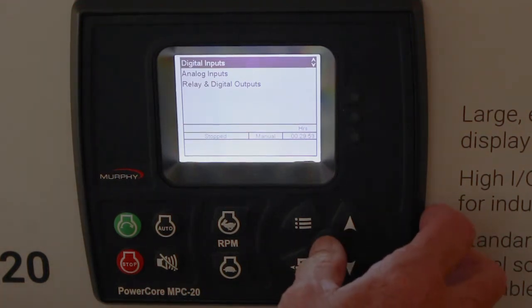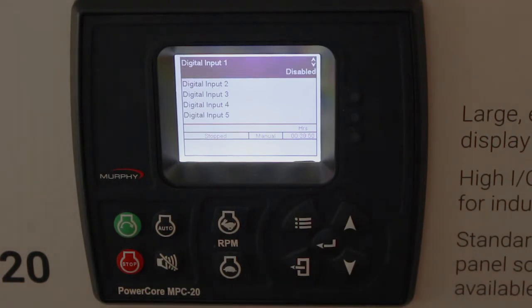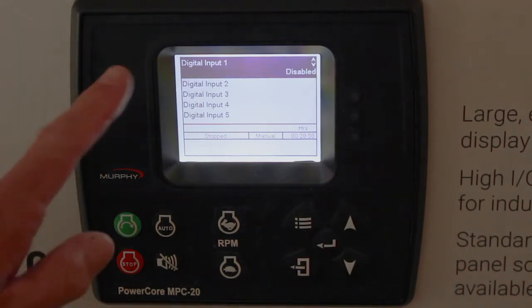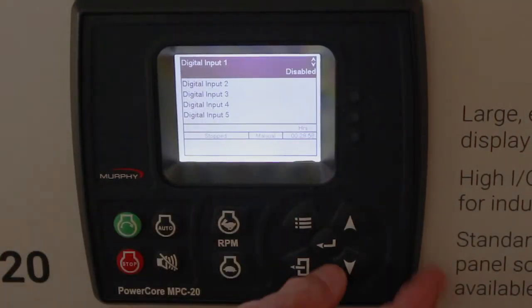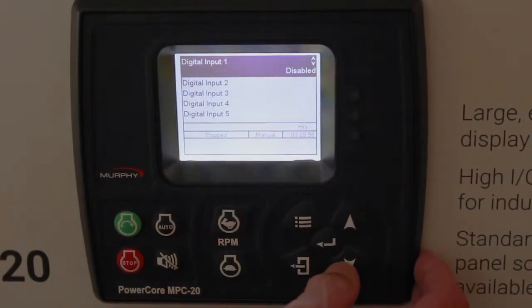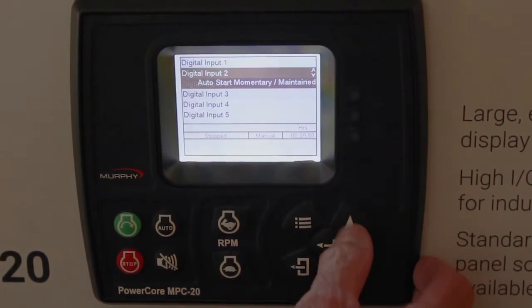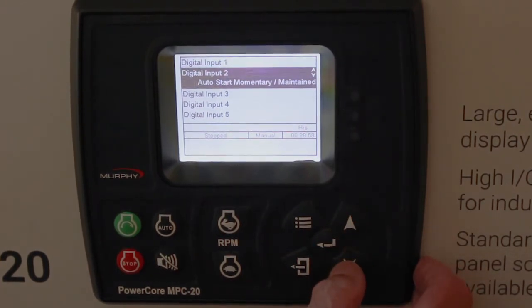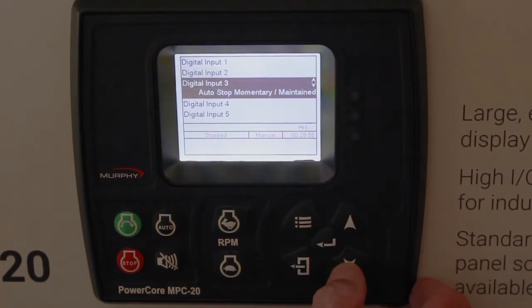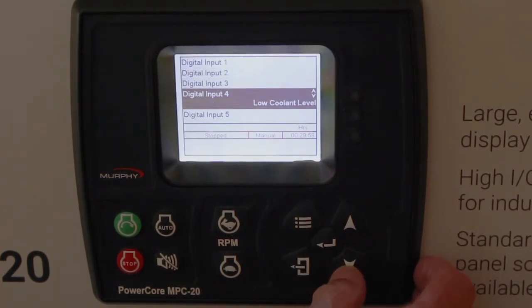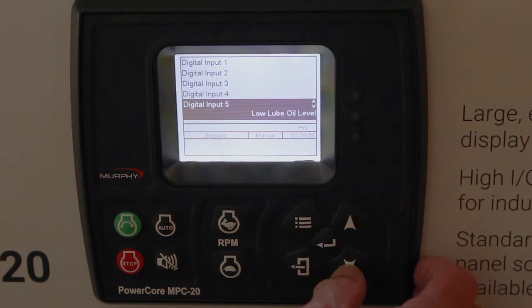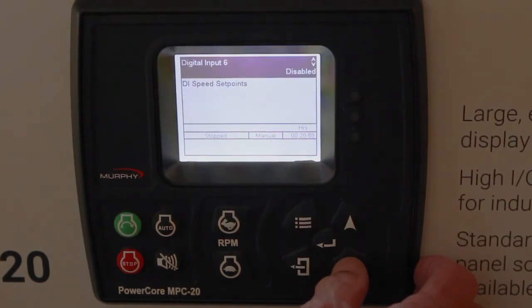Digital inputs — hit enter and you'll see digital input number one is disabled. Two and three are already set for floats: auto start maintained and auto stop maintained. Digital four is set for low coolant level, digital five is set for low lube oil, and digital six is disabled.